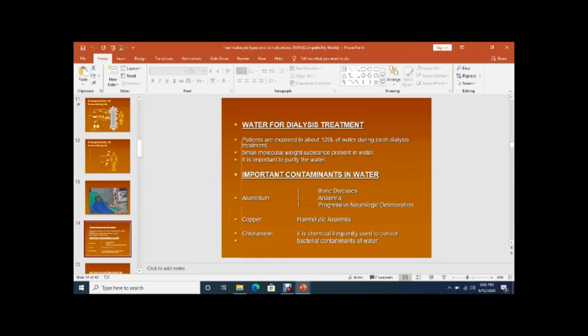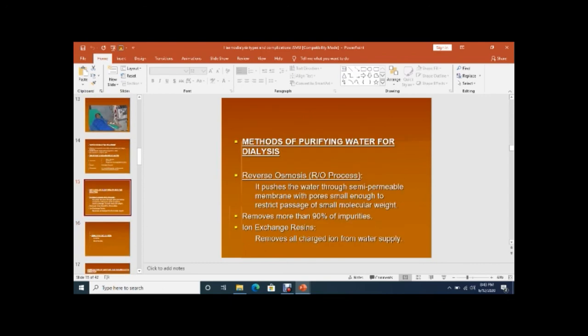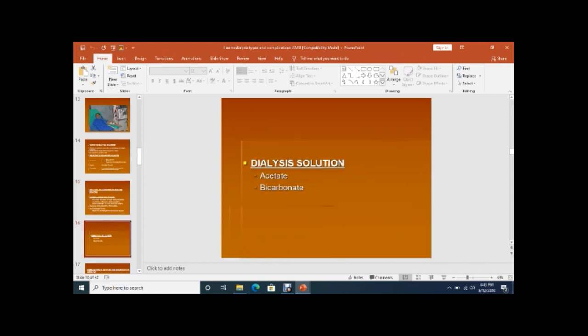If the water is not purified by an RO system, bone disease, anemia, and progressive neurological deterioration may occur. Aluminum can cause bone disease, copper can cause hemolytic anemia, and chloramine — a chemical used to control bacterial contamination of water — can also lead to serious complications during dialysis.